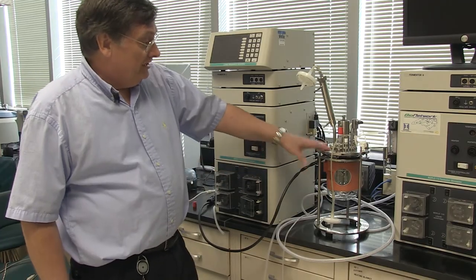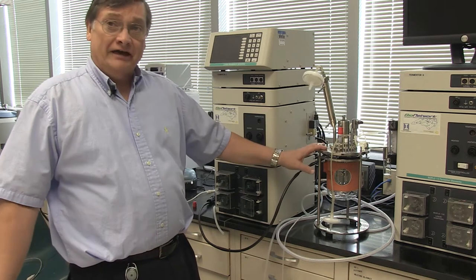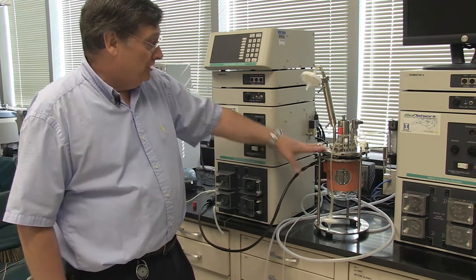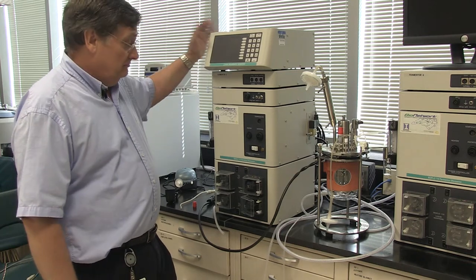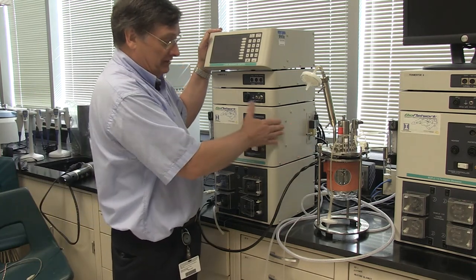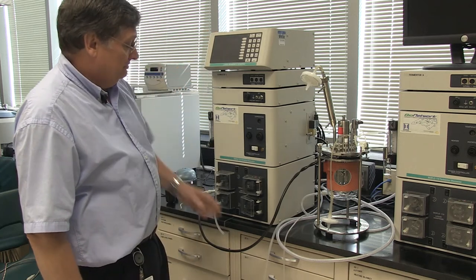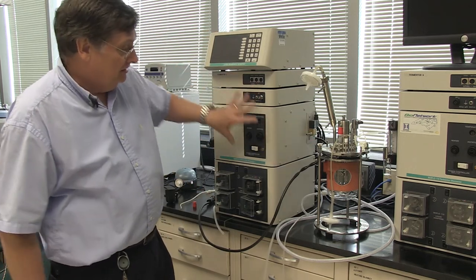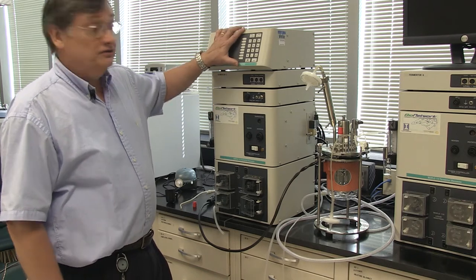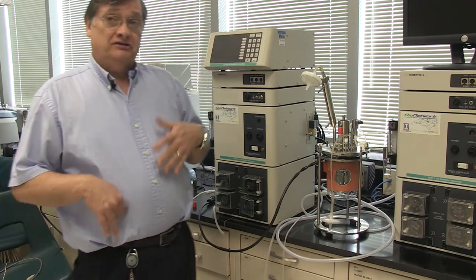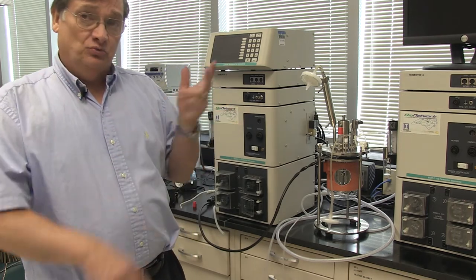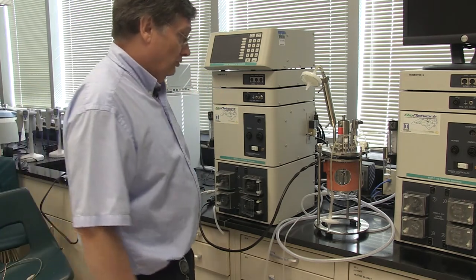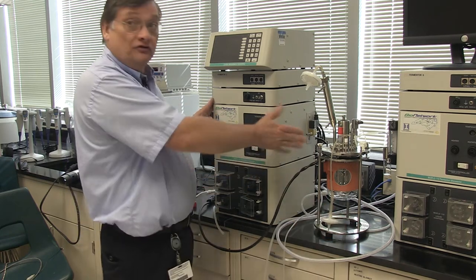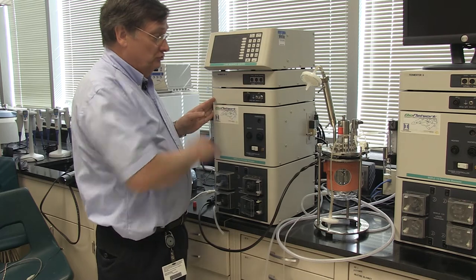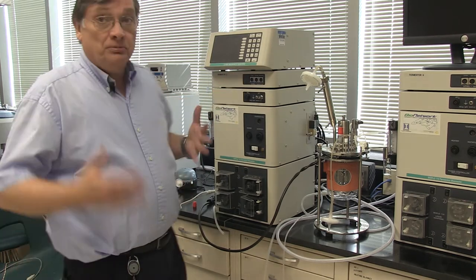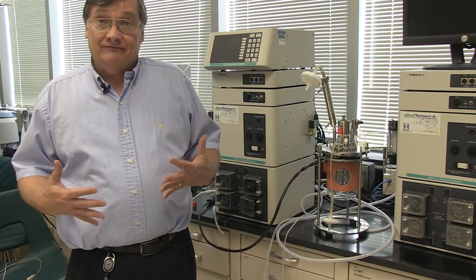Okay, so here we've got our vessel. Assume it's out of the autoclave, and it's ready to hook up to the control unit. Here we have the control unit that we're going to set up to operate this vessel. These are the various modules that we're going to connect to make our control loops, and this is the control unit that we're going to program to tell what temperature, what speed of agitation, what amount of dissolved oxygen or whatnot that we want. So we've got to connect all this telemetry up, these cables, to the device. And there's no particular order that they have to go in.